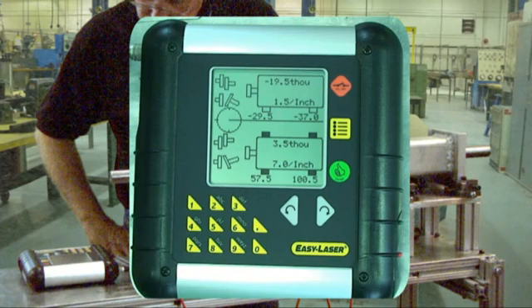To correct the vertical measured misalignment you need to adjust the feet as indicated by the two numbers below. In this case you would add 29.5 mils or thou of shims to both of the front feet and 37 thou of shims to both back feet. Remember when you see a negative number you add.